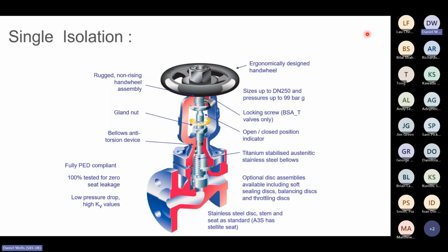So we're not likely to get that water hammer effect, but they're more forgiving against erosion. The thing to bear in mind here is a valve on a steam system should never be cast iron. We never want to see any cast iron component on a steam system. Cast iron, simply put, is far, far too brittle to stand up to the risk of any water hammer taking place. So as an absolute minimum, the ancillaries, the components should be what we call SG iron.